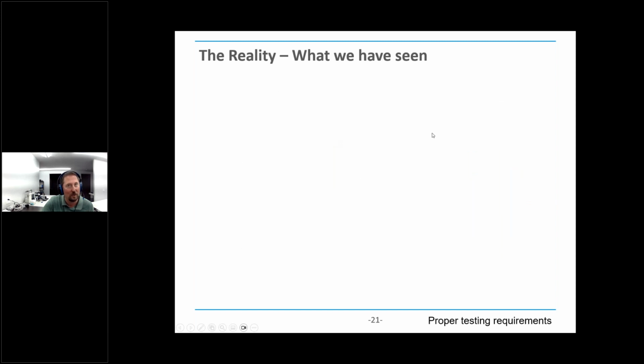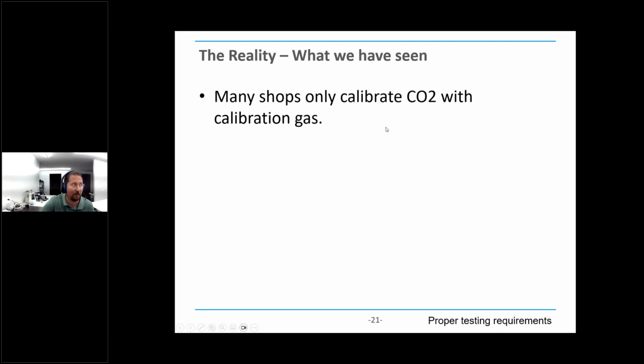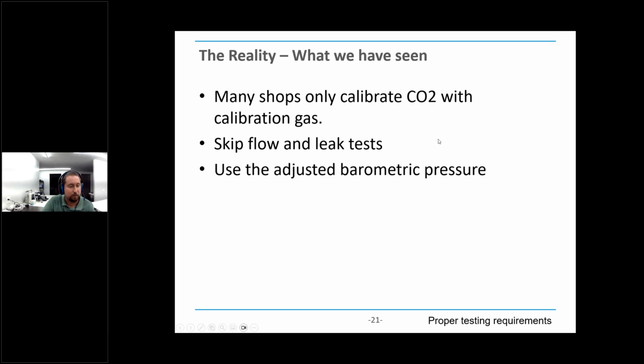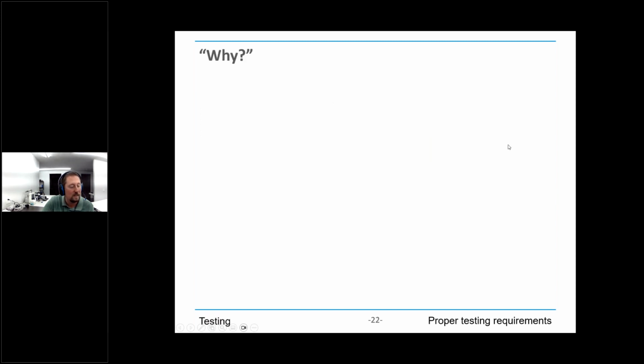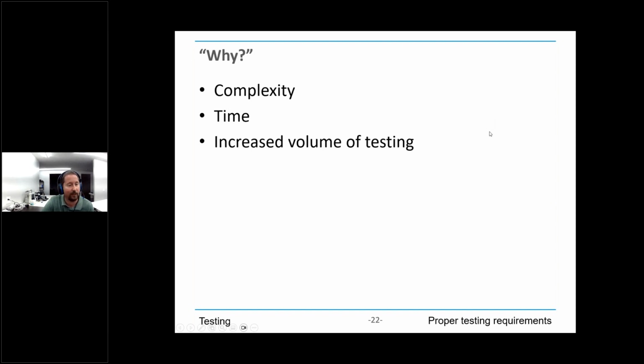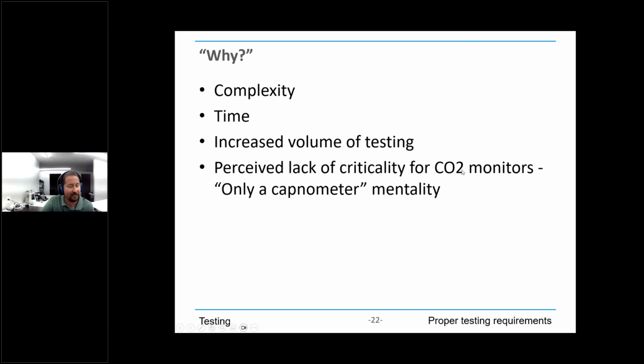And it's interesting, so when we go out and watch people, they say they follow the service manuals, but what we actually see is many shops end up just calibrating with CO2, and they skip the flow and leak tests completely, which is a mistake. They do use the adjusted barometric pressure instead of a gauge, and they often don't have the proper equipment. Those are all things that we've talked about. We ask them, why do you guys do this? What's the reason for this? Why don't you follow the service manual? And they say, oh, it's a little more complex, or it takes too much time. I just got too many devices to get through, and I understand you guys are all busy. But one thing is there's kind of this attitude of, hey, it's only a capnometer, it's not that big a deal. And hopefully this presentation's helped you understand that it's a little bit more important than you may realize.